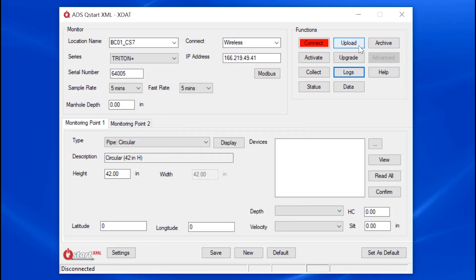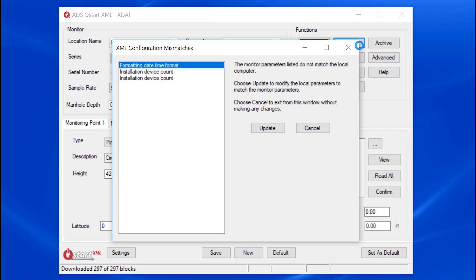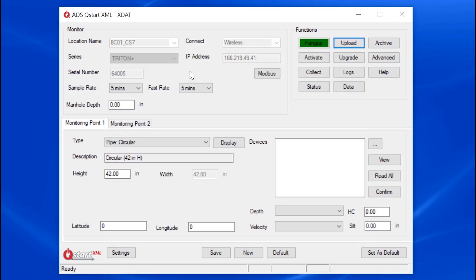QSTART XML still has the useful Upload function. Upload will connect to the monitor and upload the monitor's configuration. QSTART will compare the monitor information to what you have on the field computer and give you a warning if the parameters are different. It will give you peace of mind knowing that you can synchronize your computer settings to that in the monitor.